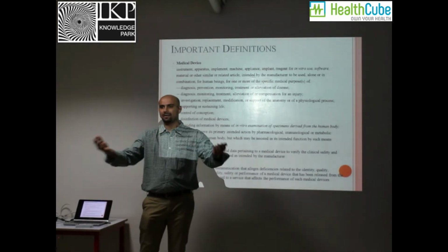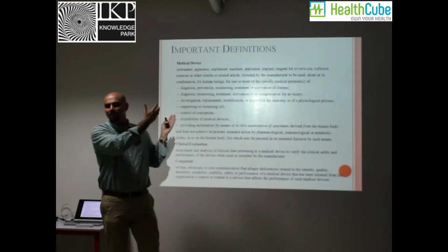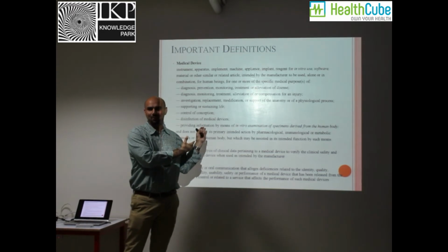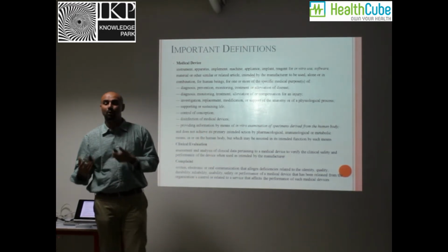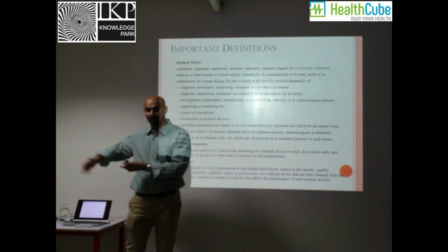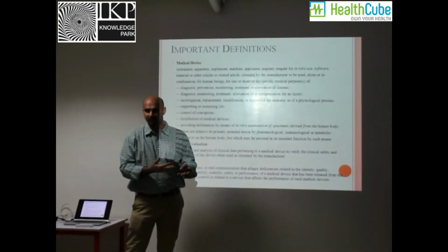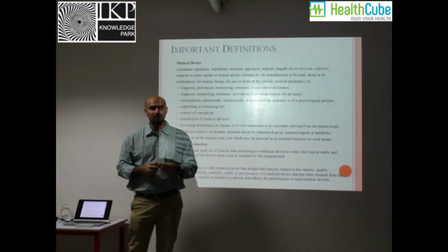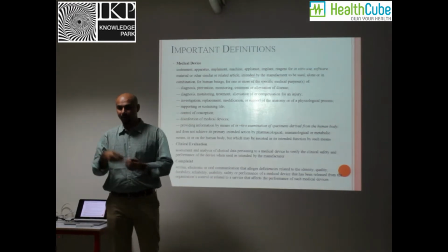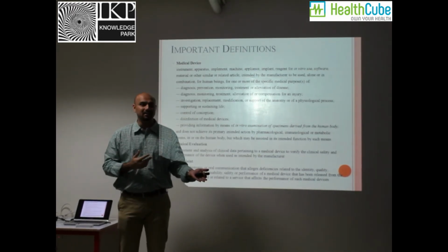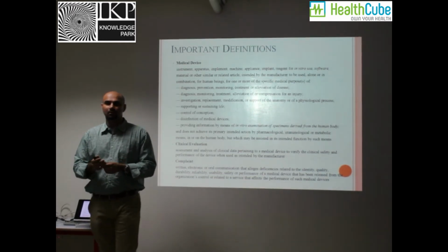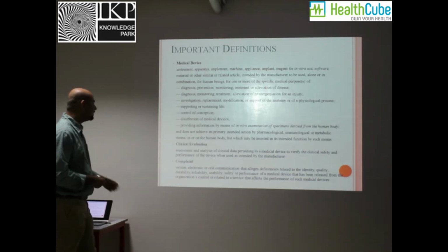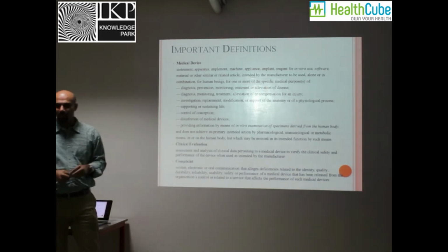Right. Before you even start 13485, you want to be very clear about where in the definition your product even qualifies as a medical device. Now, not always do you need to look at this definition, but there have been certain products that I have been working with, which in the previous version were not even defined as medical devices, right? One such product would be 3D bioprinters. Depending on your application of the 3D bioprinters, it can be classified as a medical device or not a medical device, right? So you want to understand the definition of medical device as per the standards, as per the regulatory requirements. Clinical evaluation, we'll talk about that when we talk about the clinical validation.